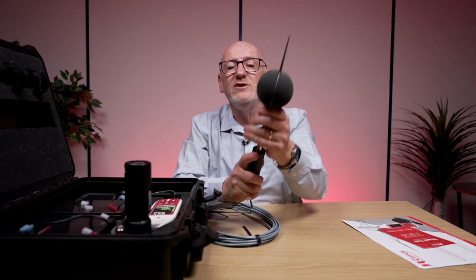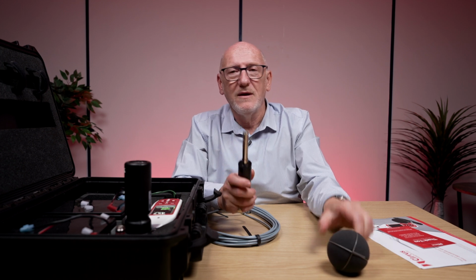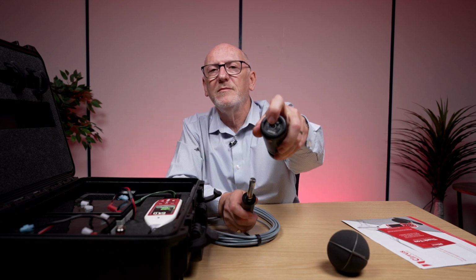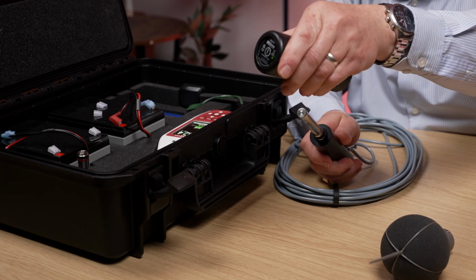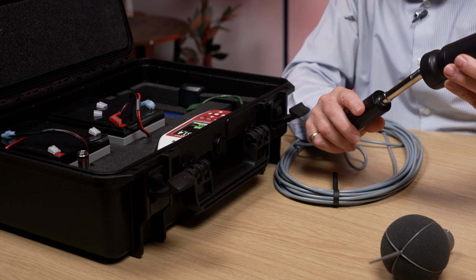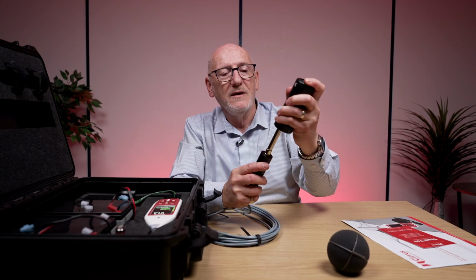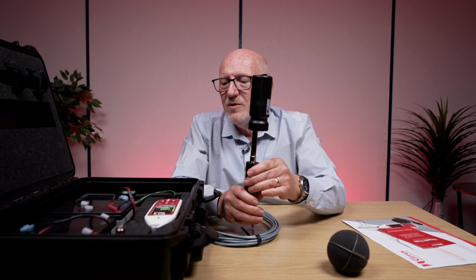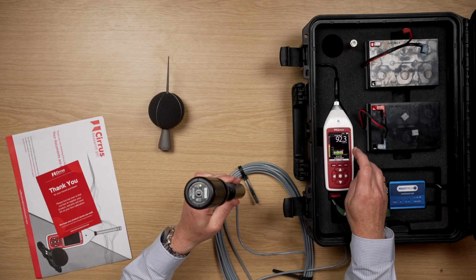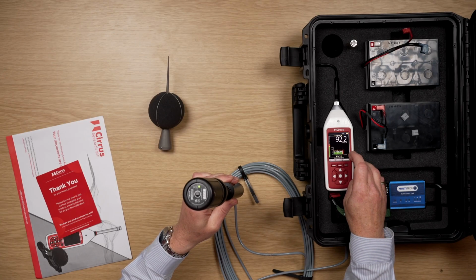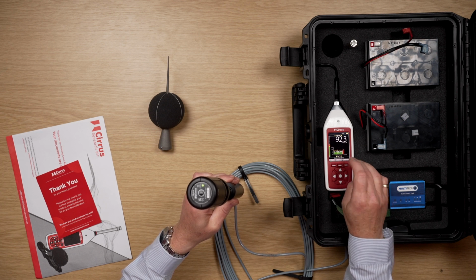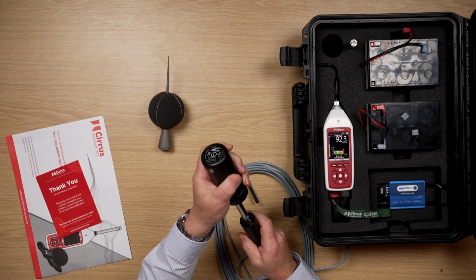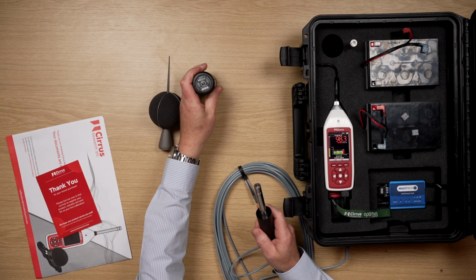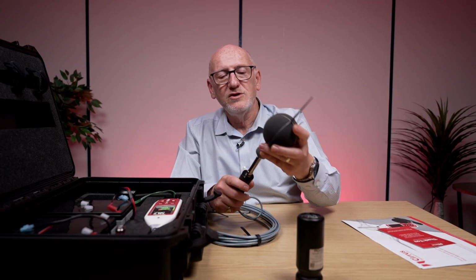We're going to put the calibrator on - you can see the green light - and put this on the end. Now that the calibrator's on, you'll see a constant noise level here, and all we need to do is calibrate by pressing the calibrate button. Once you've finished, take that off, pop the windshield back on, and you're ready to go.